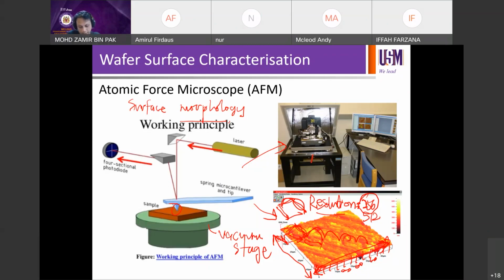Yep, 0.196 micron. Okay, that's close. 0.196, or 0.195 micron. So that means when you use 256 resolution, the spaces will be 255. So the distance between your current point to the next point will be 0.19 micron, 0.19 micrometer.